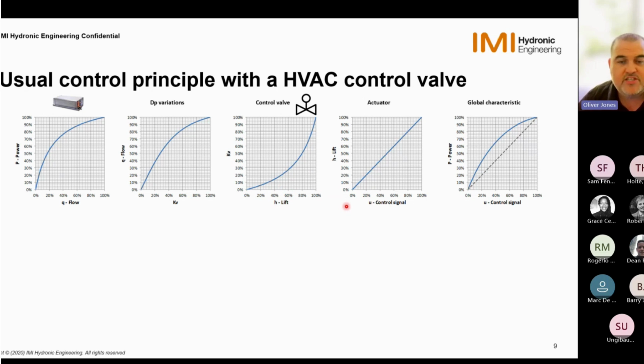So we have a system that works against us, and when combining this with a control valve that is good enough, we give a control valve with an authority of 0.25, which is the minimum authority we should always meet on 2-port control valves. We get a global circuit characteristic of the power output of the unit, which is shown in P, in function of the control signal, which is U, coming out of the controller, which is nonlinear and which would not be easy to control at these initial steps of demand. So you can see the linear dotted perfect line, and this is realistically where our global characteristic is coming from.